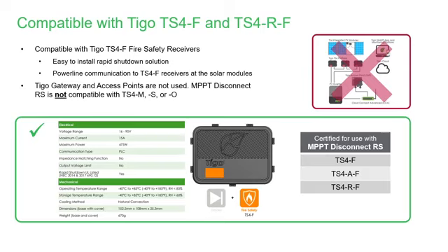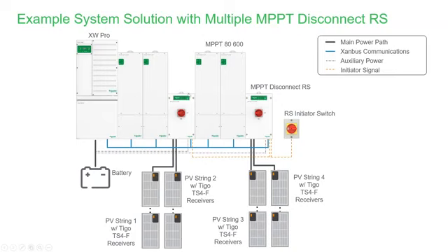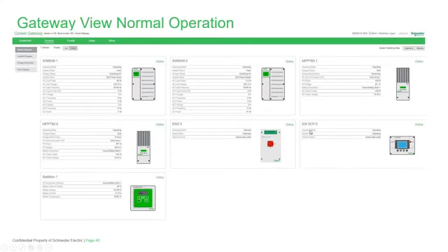On the roof, under each module, then you have the Tigo F series, which are communicating with the Schneider Disconnect RS via power line. So you don't need to run a communication cable. You just simply mount these under each one of the modules, and then the disconnect will be triggered by the communication over the power line. Because the RS disconnect is in the Xanbus network, it also shows up on the gateway interface as well as inside too. So you actually can see which state it is, if it has triggered a rapid shutdown or if it's a normal operation, because it is connected in the same network.